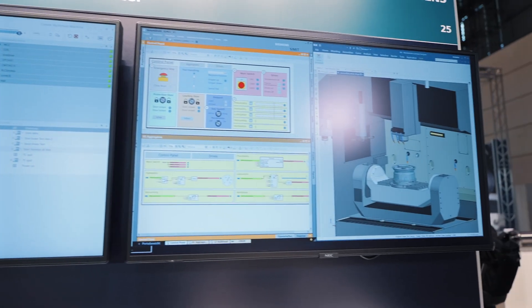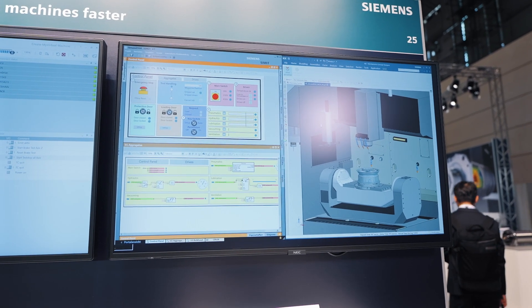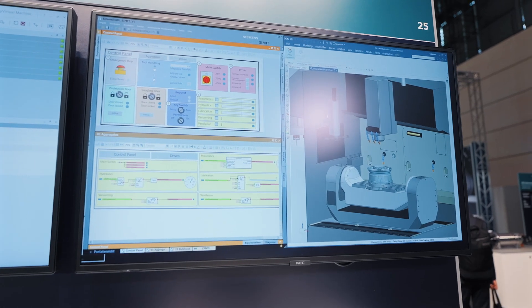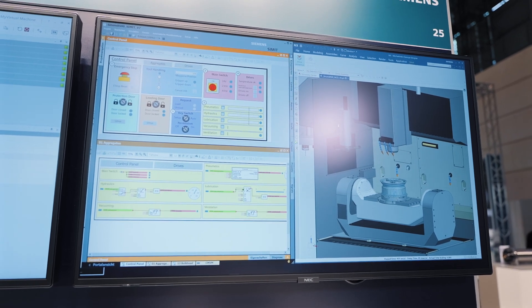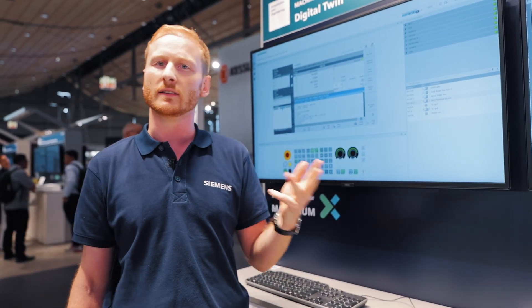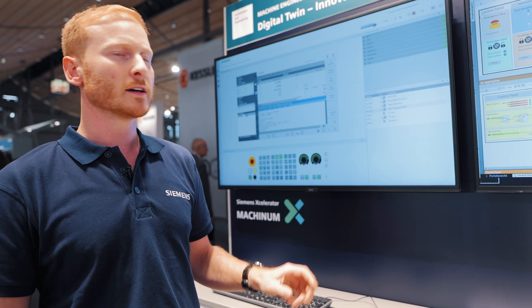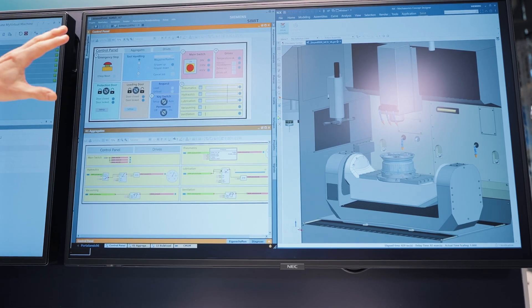In order to carry out virtual commissioning and get feedback from the field, we need a counterpart to our control. You can see on the right-hand screen — that's the next component of our digital twin — our virtual behavioral model. The behavior of all components in the machine is mapped: the control cabinet components, components inside the machine such as hydraulic pumps, pneumatic units, cylinders, valves, and so on. Here the counterpart of the controller is mapped and signals can be generated.